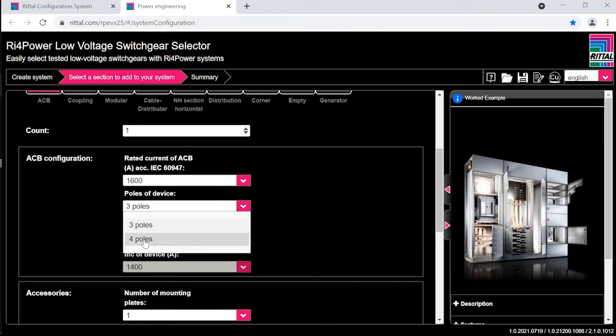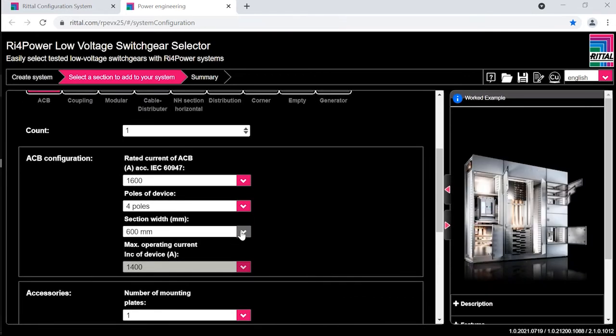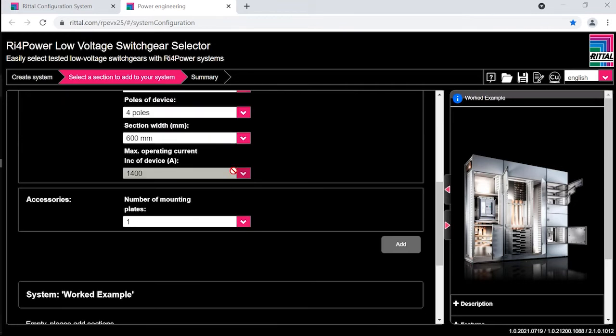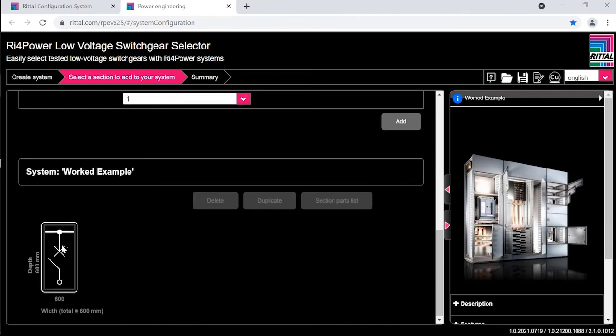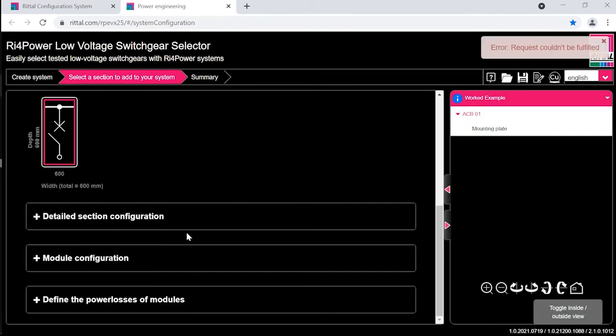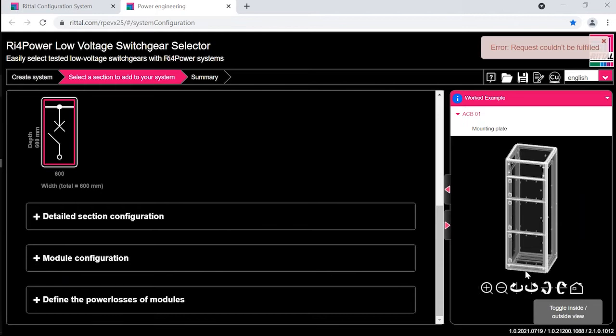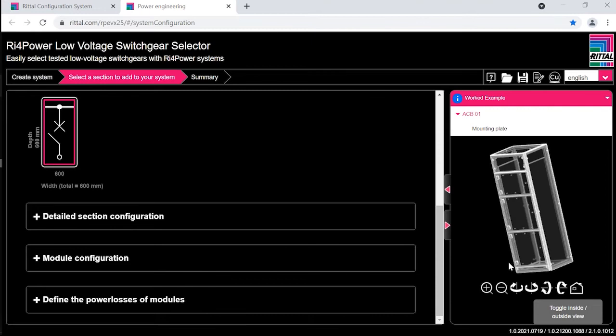It is a 4-pole circuit breaker, default, so a minimum of 600 wide. The maximum of that particular arrangement is 1400 amps, and we have 1 mounting plate which fits above the ACB. When we click add, it selects the circuit breaker section. From there, you can see the 3D drawing, which is quite useful. Now we look at the detailed specification of the circuit breaker.